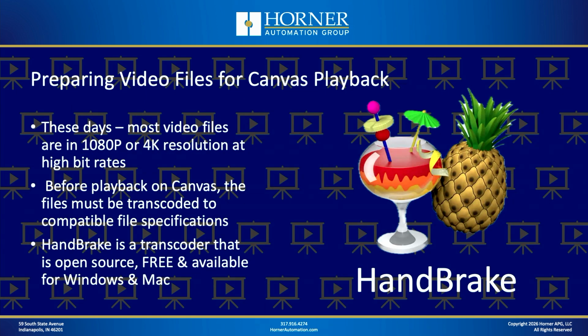Now, you can't just take any old video file and put it on a memory card and play it back on a Horner OCS. Remember, the Horner OCS is primarily a PLC, so it has to be able to play video and still do its job perfectly, the important job of controlling the machine. So most of the video files that you may want to play on Canvas are going to start out maybe as a 1080p or a 4K resolution file with a high bit rate. But before you play it back on Canvas, you need to transcode that file to a compatible file specification.